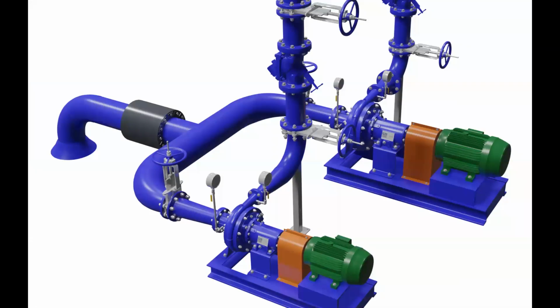And all this because that small pump was happily pumping along its flow until the bigger pump came on, started pumping through the same header, and increased all the back pressures because now there's so much more friction. That little pump got pushed back on its curve, reduced flow, hit that left-hand side and started to induce recirculation cavitation. So again, if these two pumps were not designed to operate together, then make sure they don't operate together. Many times with a smaller jockey pump and a larger pump, they don't operate together. The jockey pump is designed to go offline before the big pump comes on.